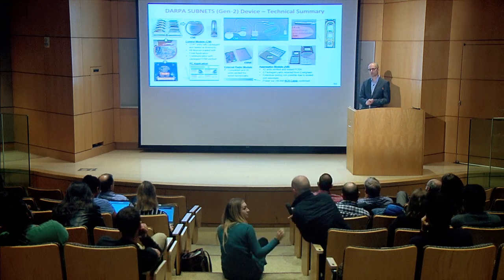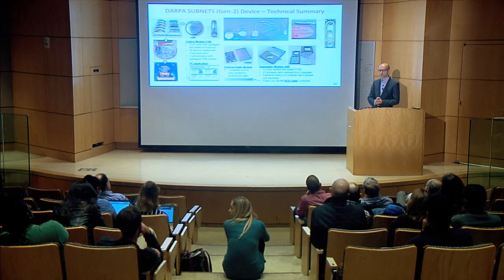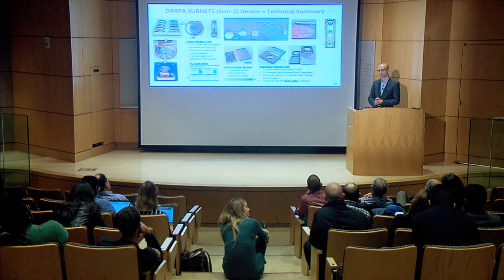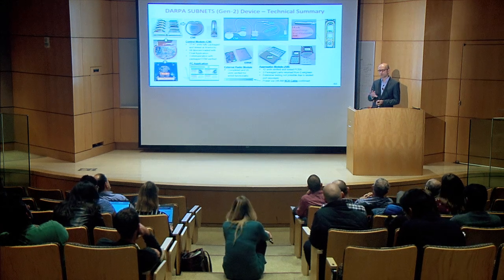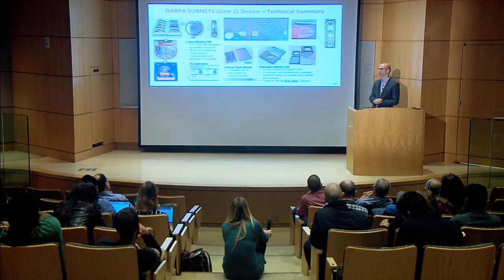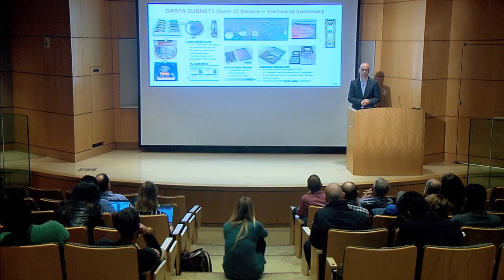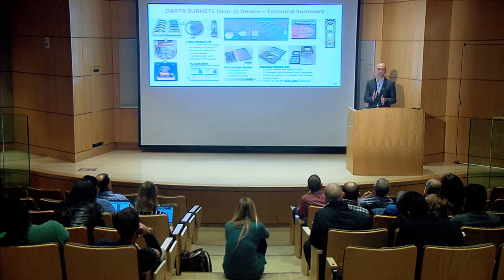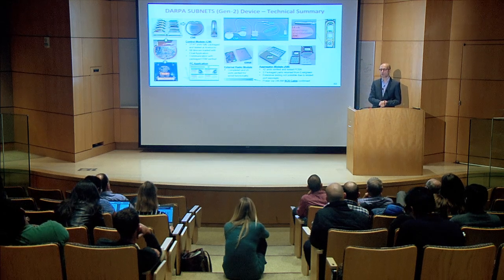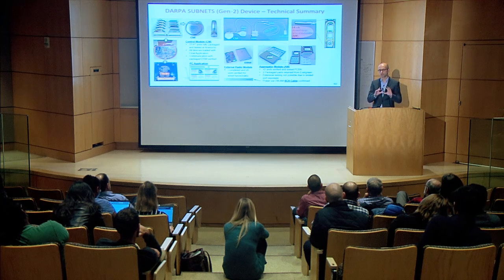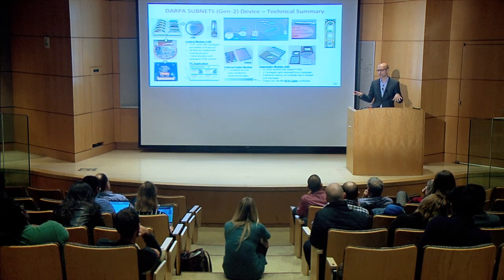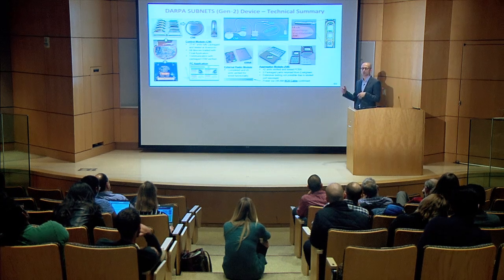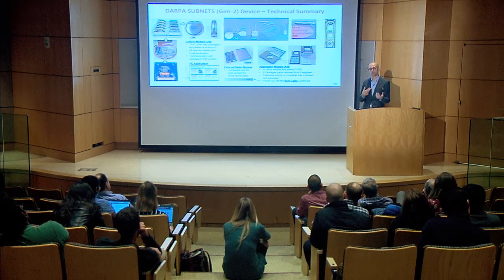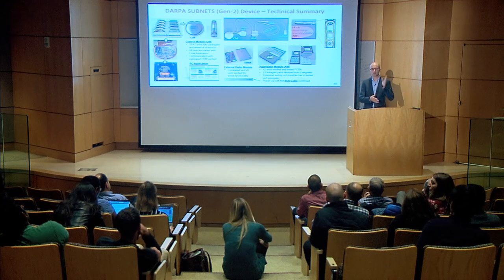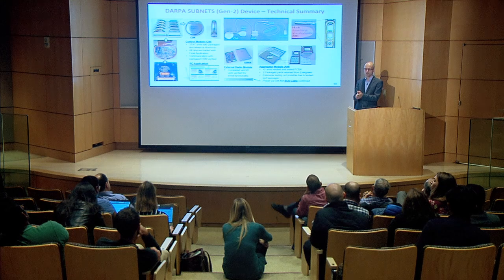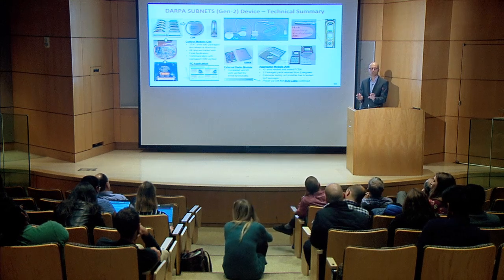Yeah, it's a good question. So like I said, you have more contacts than what you need. So you first go through sensing to figure out which contacts are relevant. Out of 256 contacts, you will find that anywhere between 15 and 40, let's say typically 30 contacts, are the ones that you care about. And you do that in multiple stages. You first do a system identification process. No stimulation, you just see the baseline, and then you figure out the biomarkers, and then you do the stimulation and make refinements. At the end of that system identification process, you then calculate which locations, which channels you need, okay?